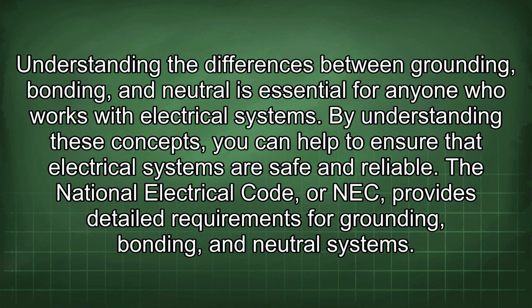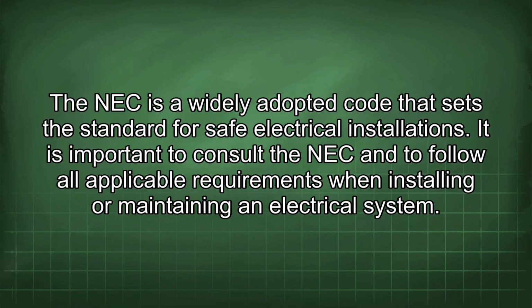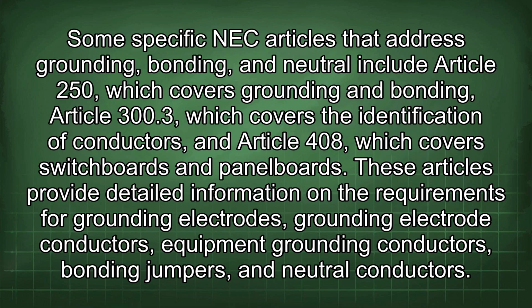Understanding the differences between grounding, bonding, and neutral is essential for anyone who works with electrical systems. By understanding these concepts, you can help to ensure that electrical systems are safe and reliable. The National Electrical Code, or NEC, provides detailed requirements for grounding, bonding, and neutral systems. The NEC is a widely adopted code that sets the standard for safe electrical installations. It is important to consult the NEC and to follow all applicable requirements when installing or maintaining an electrical system. Some specific NEC articles that address grounding, bonding, and neutral include Article 250, which covers grounding and bonding, Article 300.3, which covers the identification of conductors, and Article 408, which covers switchboards and panelboards.